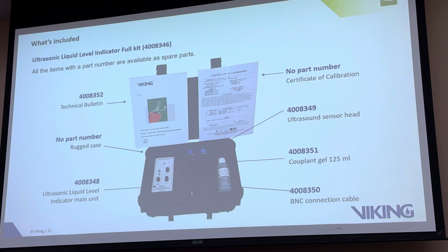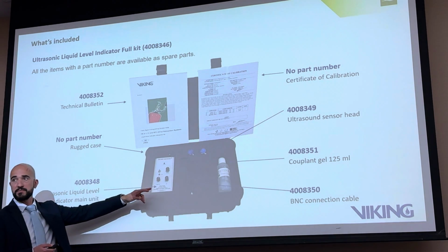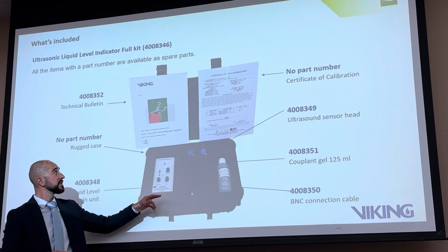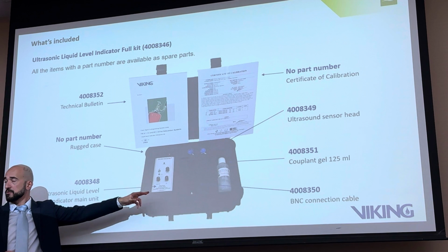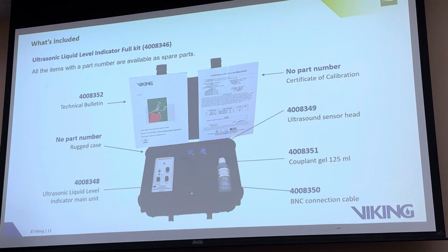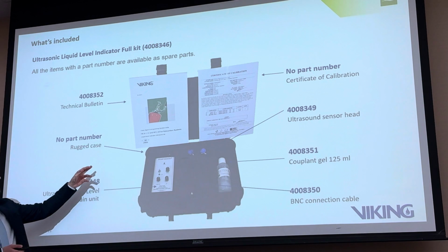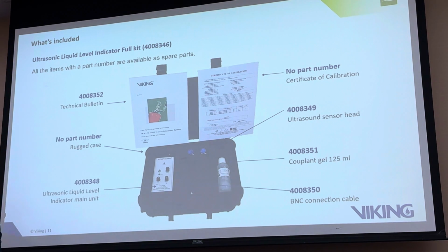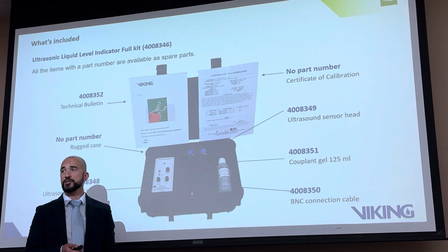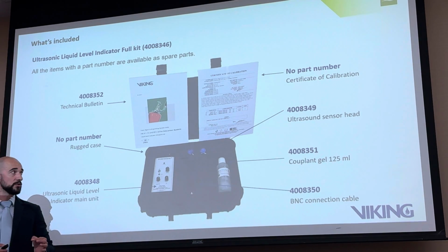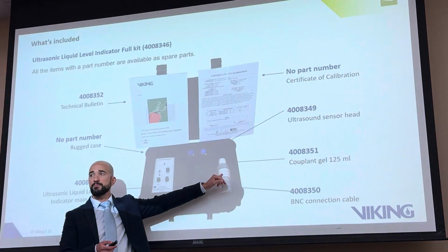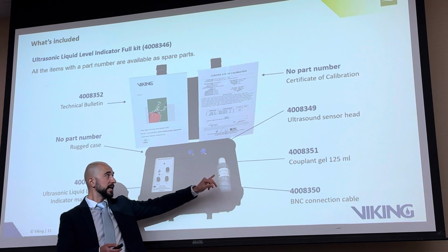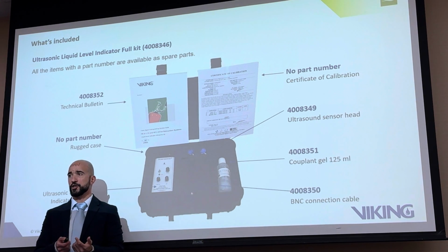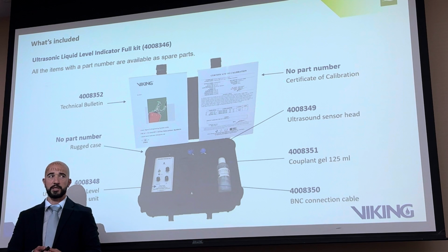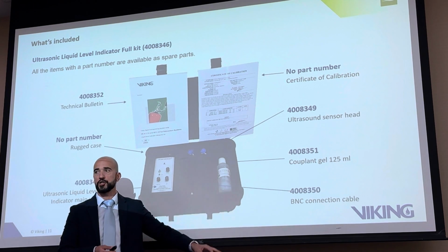We acquired a liquid level indicator kit. What's in it for us? It comes with the main device everyone is seeing right now, a rugged case prepared for field operation, the manual, and a calibration certificate unique to that particular device. It also comes with two samples of couplant gel, two sensors—one general and one spare in case of breakage—and the BNC connection cable.